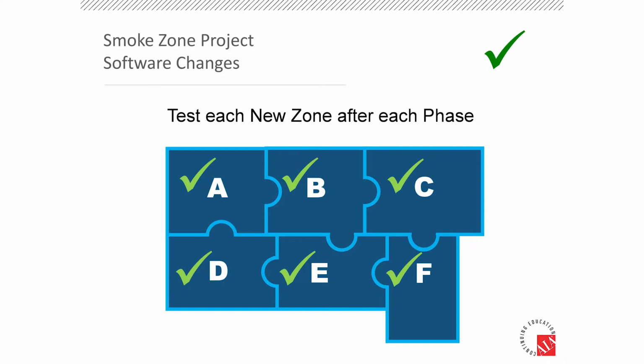So interestingly, what they came up with was, yeah, they'll take our test and use it to pre-test zone A, then B, then C, after each one. But as commissioning agents, you'd be well within your right to ask: what happens, Dan, when I test A and it's all great, but the next weekend I come in and do B? What about the software changes I put into that same panel that A is in, and now I'm putting B kind of meshed in there between it?